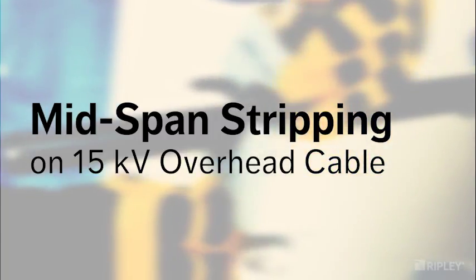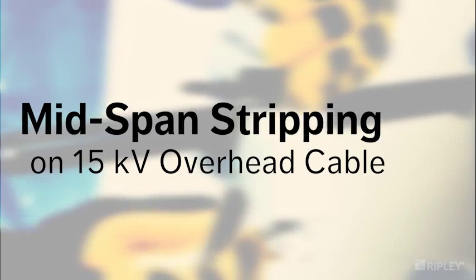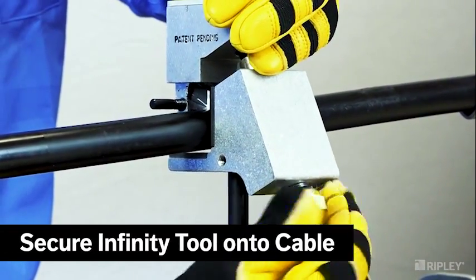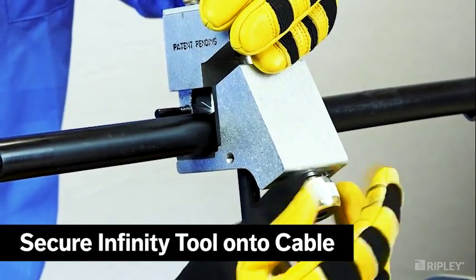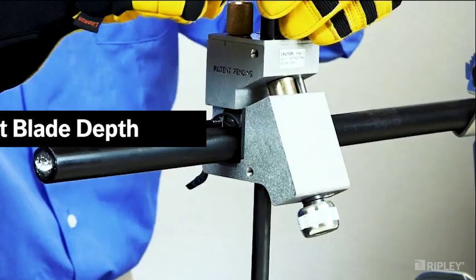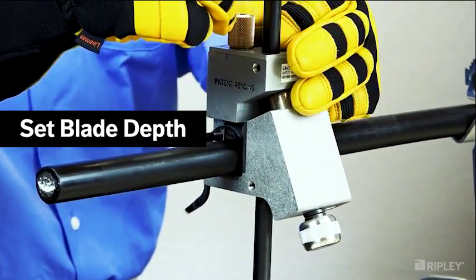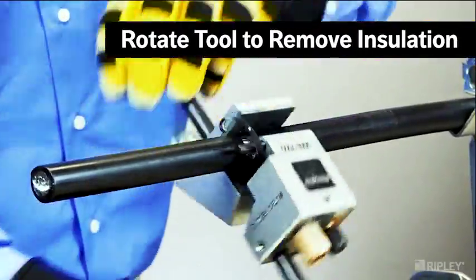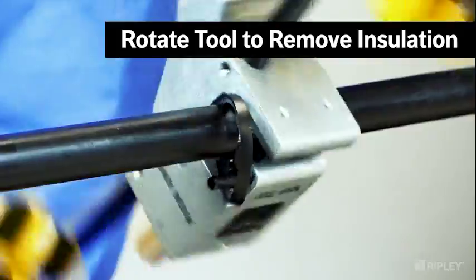To begin stripping the insulation from the mid-span on 15 kV overhead cables, secure the Infinity around the mid-span where the strip length has been marked. Adjust the blade angle to 0 degrees for a squared edge and slowly adjust the blade depth down to the conductor. Rotate the tool to remove a channel of insulation to expose the conductor.